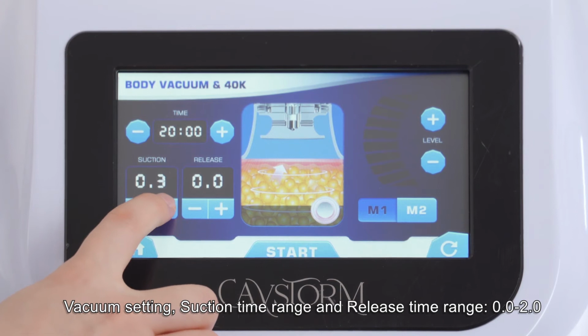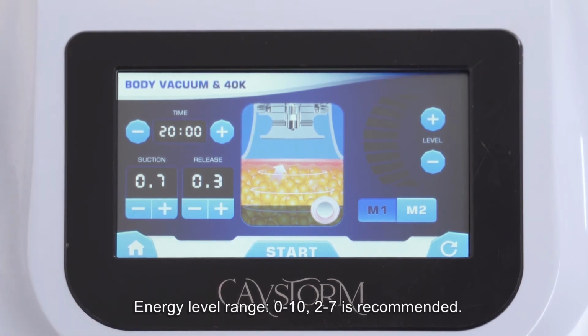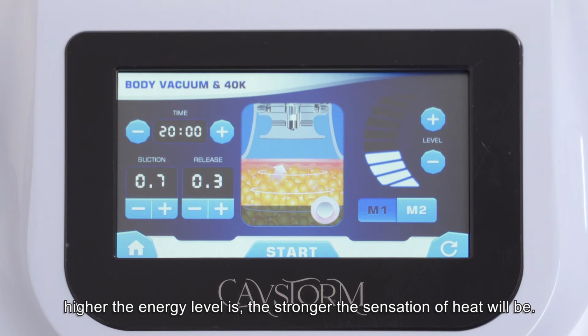Vacuum setting. Suction time range and the release time range 0 to 2. Energy level range 0 to 10. 2 to 7 is recommended. The higher the energy level is, the stronger the sensation of heat will be.